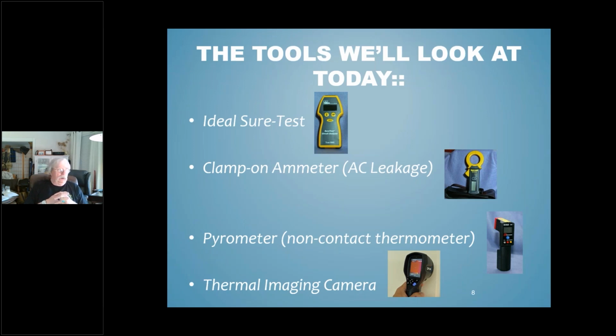And when I say that, we're looking at very small values. For those of you that do AC work, understand that today we have a 30 milliamp whole boat protection requirement via the ELCI devices. 30 milliamps is not a lot. I mean, there's 1,000 milliamps in 1 amp of AC current. So unfortunately, this also means that you're not going to be able to effectively check for AC leakage with your standard AC clamp meter. It just doesn't have the sensitivity you need.